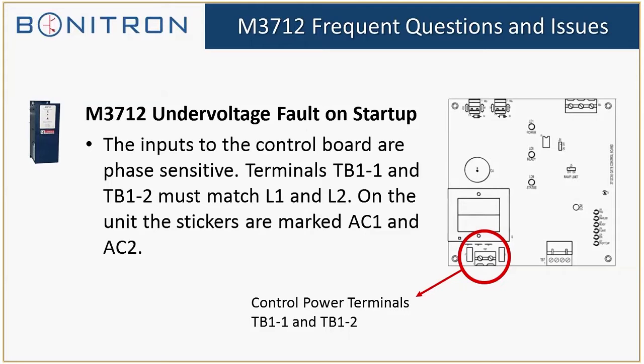By and large, I find that a lot of customers don't read the manual for the M3712, or if they do read the manual, they have a lot of questions about startup. Basically, we do require that there's a separate power coming in from the actual power terminals, L1 and L2, to what's powering the control board. The reason for this is we recommend using a reactor, but the power going to the control board needs to come from in front of the reactor. I'm not certain of the reason for this, but basically it's a reactance issue and what the control board needs. So the control board does need its own separate power source from the actual L1 and L2.